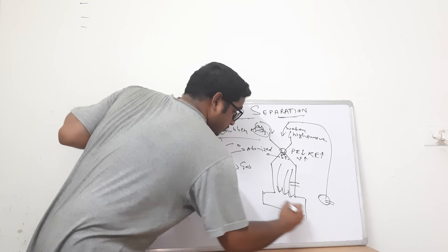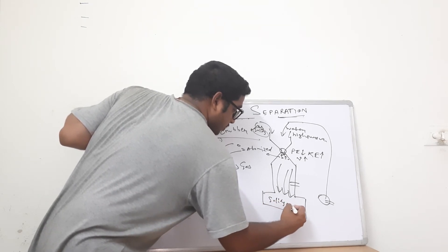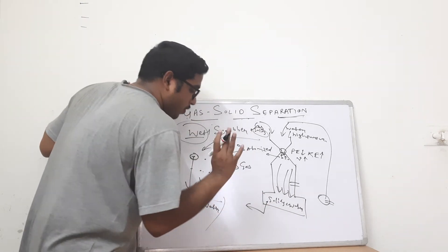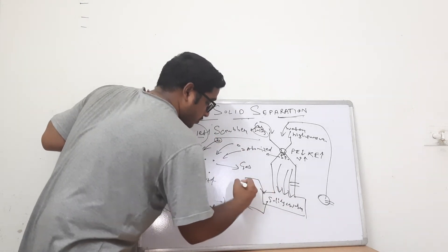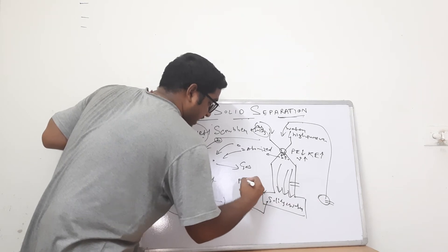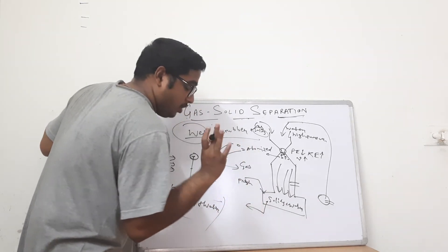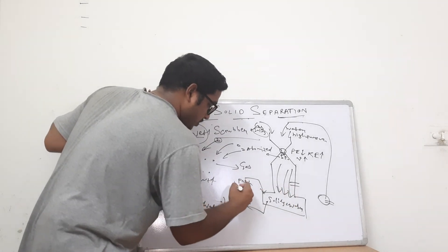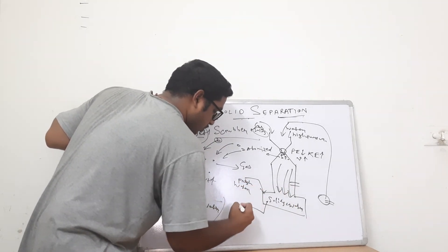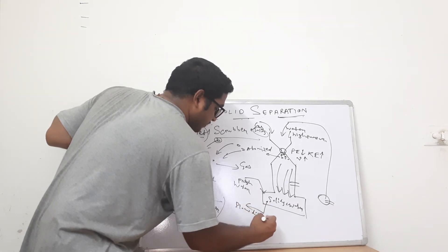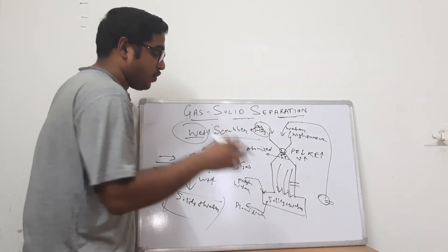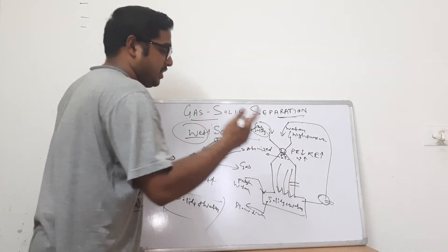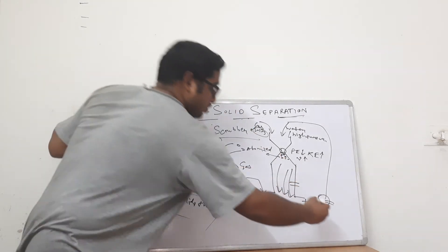The atomized droplets of water take off the solids, wet them, and deposit at the bottom where the solids plus water are collected. We continuously blow down a portion of this system and add fresh water to maintain the TDS or TSS — that is, the solids concentration in the water. We then recirculate this water from the reservoir back into the system using a pump.